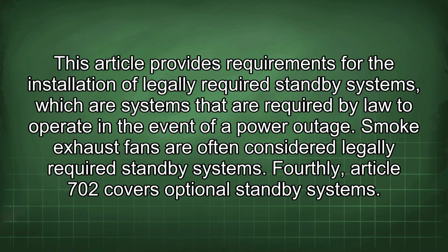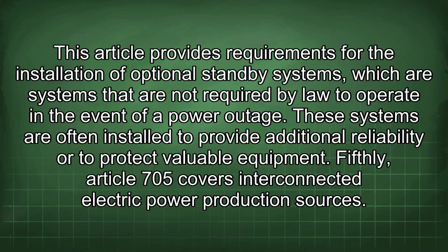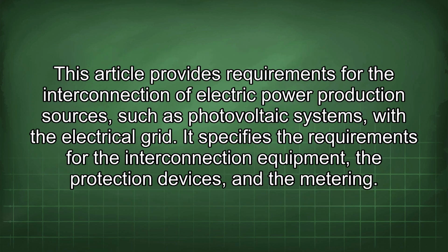Fourthly, Article 702 covers optional standby systems. This article provides requirements for the installation of optional standby systems, which are systems that are not required by law to operate in the event of a power outage. These systems are often installed to provide additional reliability or to protect valuable equipment. Fifthly, Article 705 covers interconnected electric power production sources. This article provides requirements for the interconnection of electric power production sources, such as photovoltaic systems, with the electrical grid. It specifies the requirements for the interconnection equipment, the protection devices, and the metering.